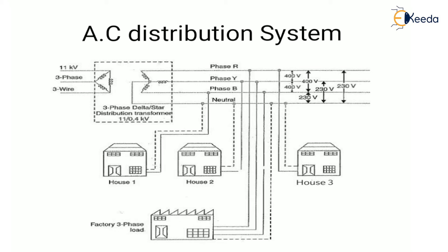In secondary distribution, the electrical power at 11 kV is delivered to the distribution substation, which is located near the localities of the consumers. Here the voltage is stepped down to 400 V, 3-phase 4-wire. The voltage between any two phases is 400 volts, and between any phase and neutral is 230 volts — single-phase domestic loads are connected at 230 V, and three-phase motor loads are connected at 400 V.